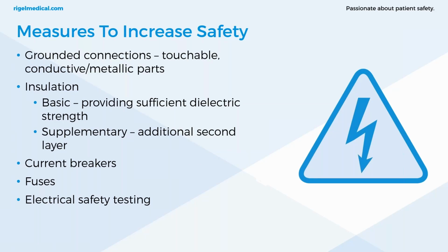There are several specified safety barriers within the circuitry of equipment which guarantee that these leakage currents are not going to be a hazard to the user and the patient. When we talk about electrical safety in NFPA 99, we're just ensuring that it continues to be performing safely during its medical device life cycle. One of the main ways of doing that is a grounded or earth connection, and this applies to class 1 equipment only. It relies on a protective earth, and that provides a low resistance earth path for all leakage currents to flow to the ground if a patient or user was to come into contact with any exposed conductive parts.